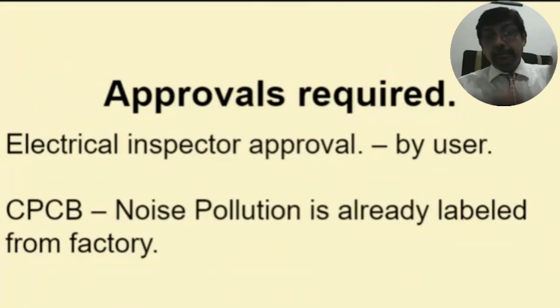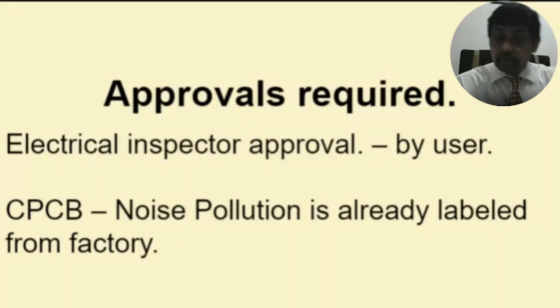The engine has the pistons which keep on running up and down, and the tappet. So the pistons, the cylinder rods, and this within the cylinder of the engine, they make the noise. So this noise is ensured to be within the limits by the engine manufacturer, and a CPCB certificate is riveted there on the engine. So there is no requirement of CPCB to be done by the customer. Customer only has to take the electrical inspector approval.